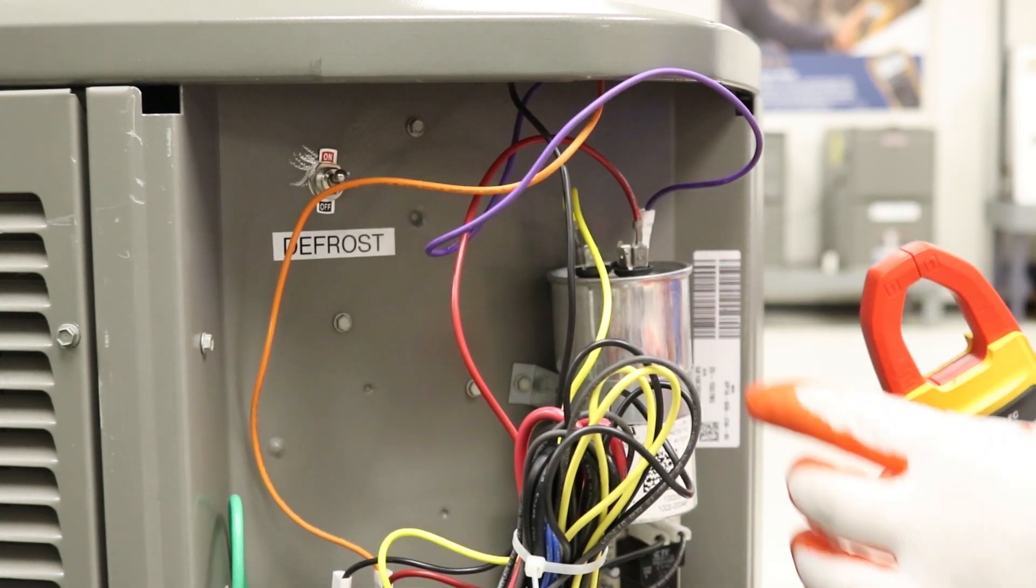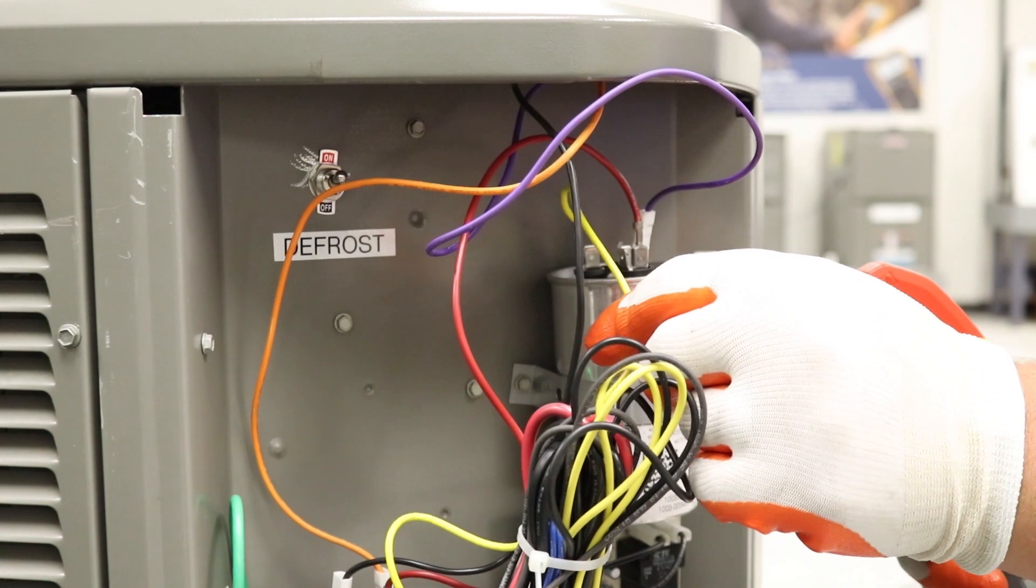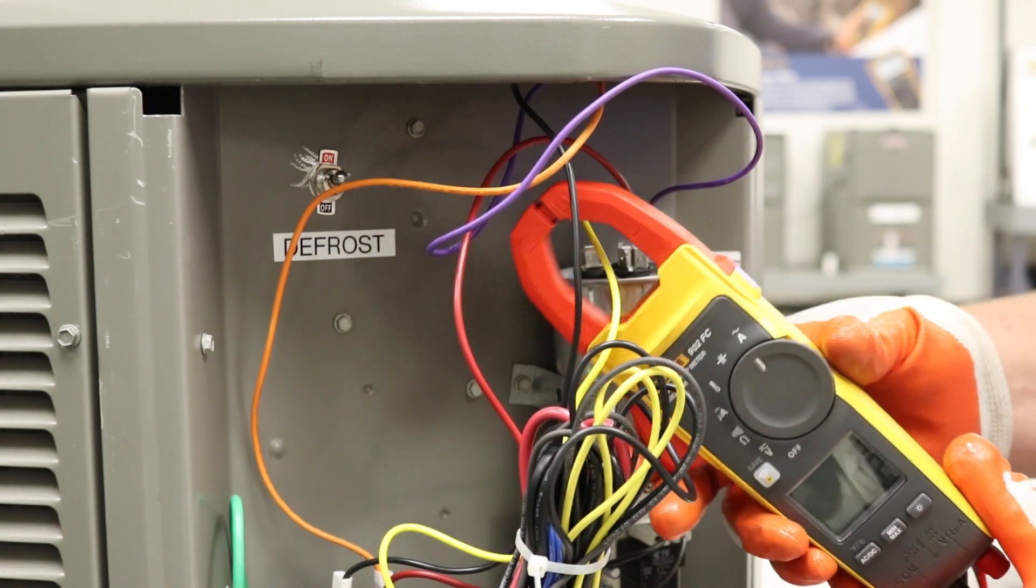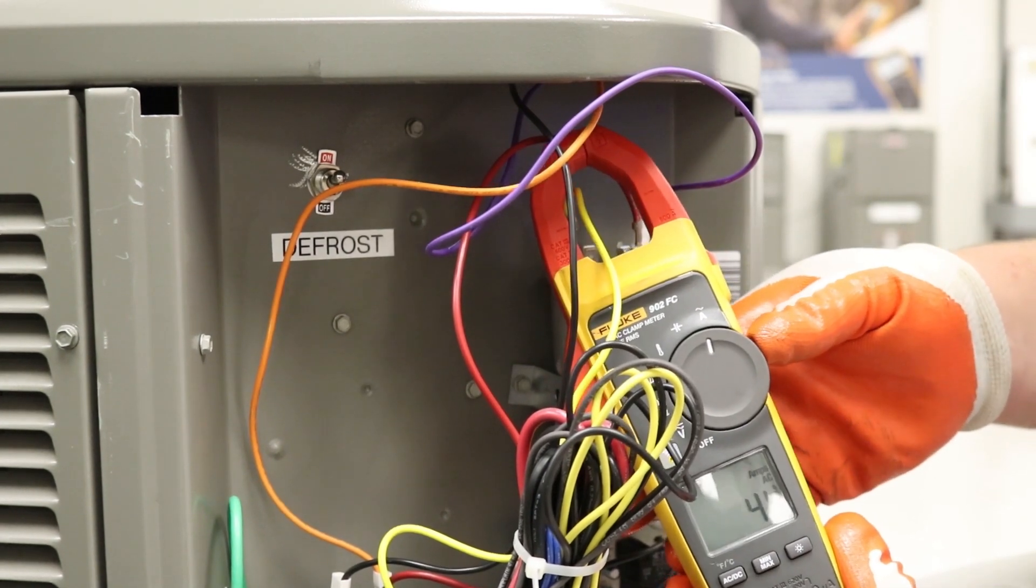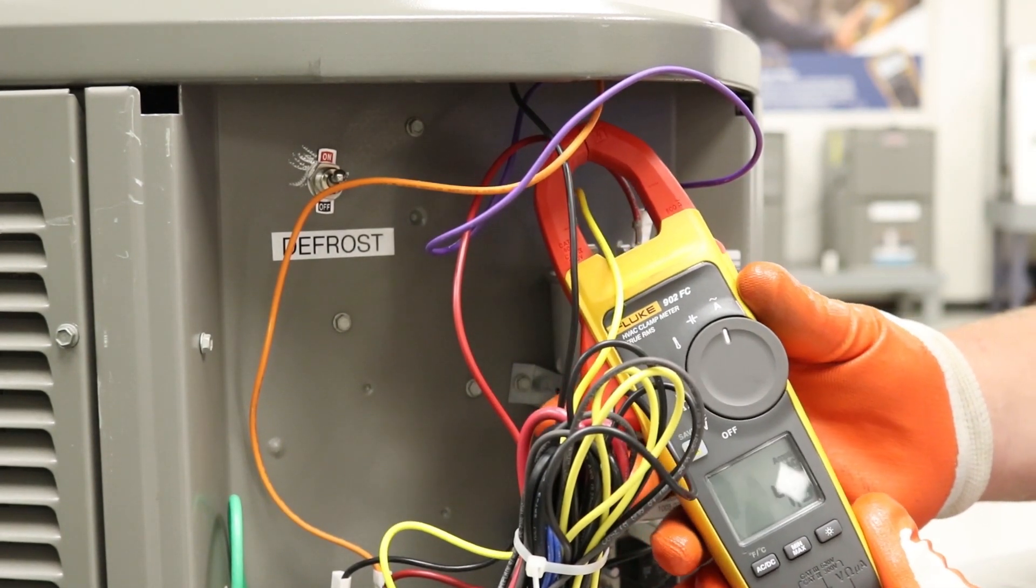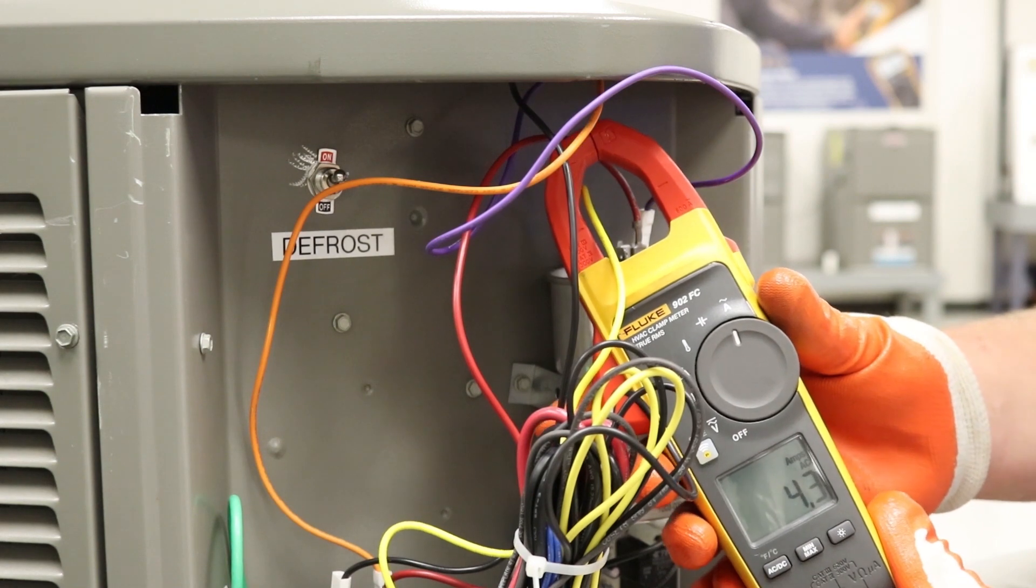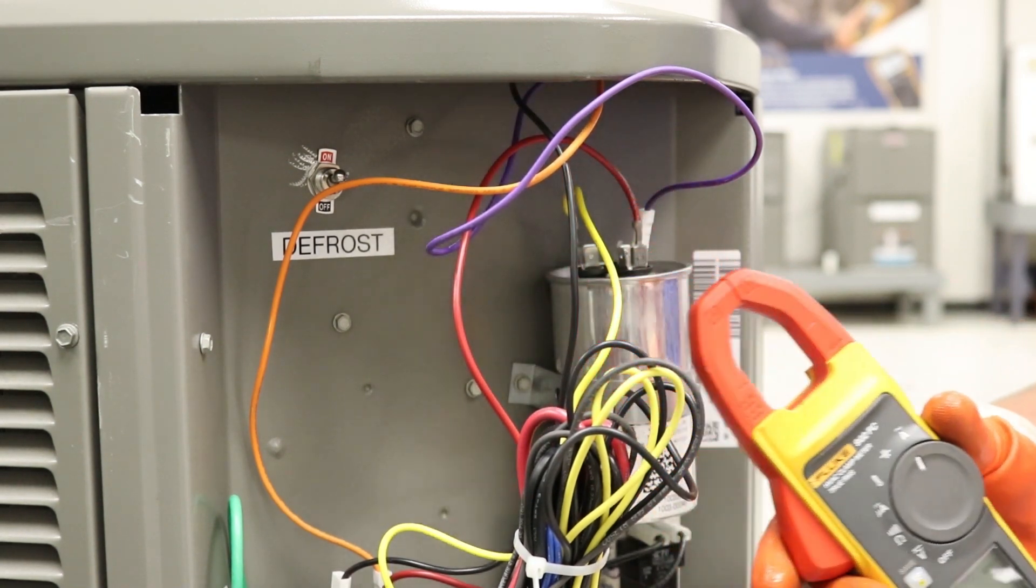We're going to do the same thing across the hermetic terminal or the compressor terminal. We're going to go ahead and hook up our meter to that. And as you can see, it says that our reading is 4.4 amps. So 1.0 and 4.4 amps. You're going to want to write both of those numbers down.